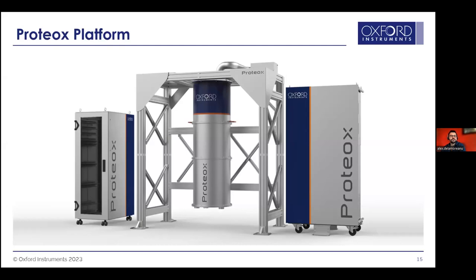So the Proteox looks like that. This is the platform, as you can see in the picture. Let me just show a pointer, maybe you can see my pointer. In the middle, it's the cryostat with the anti-vibration frame. On the right-hand side, you can see the gas handling system. And on the left-hand side, you can see the control rack where you have your laptop, the magnet power supply, if you have one, all the temperature controllers, and basically all the electronics. This platform is common to the different Proteox we have.